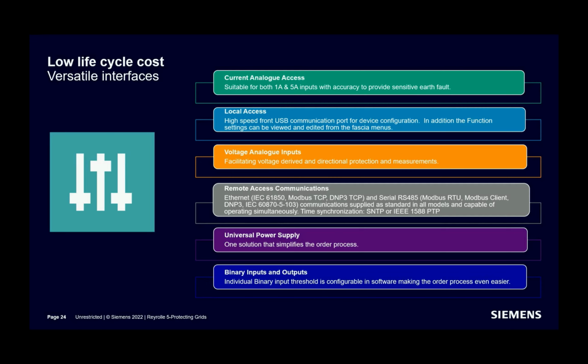The rear serial RS485 port provides all major serial communication types. No need to mention them at all. Well, all these communication protocols are supplied as standard in all models and capable of operating at the same time. Both serial ports, both Ethernet communication, and as I said now, you can operate with IEC 61850 bundled with Modbus TCP and DNP3 TCP. And you have the universal power supply. The range is 24 volt DC to 250 volt DC, or when it comes to AC, it's 100 volt AC to 230 volt AC. And it, of course, operates both 50 and 60 hertz.